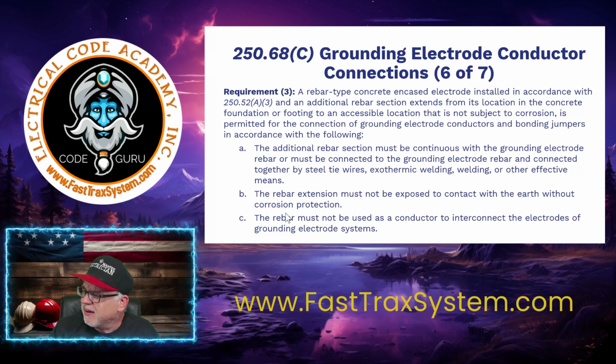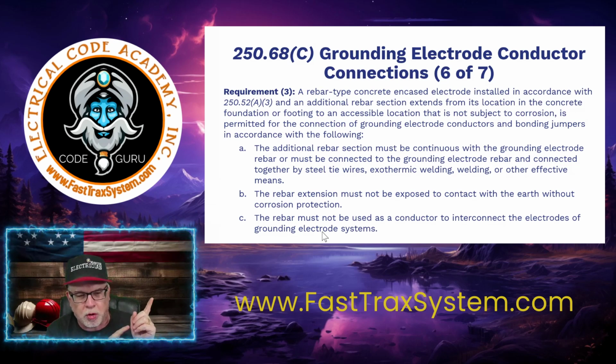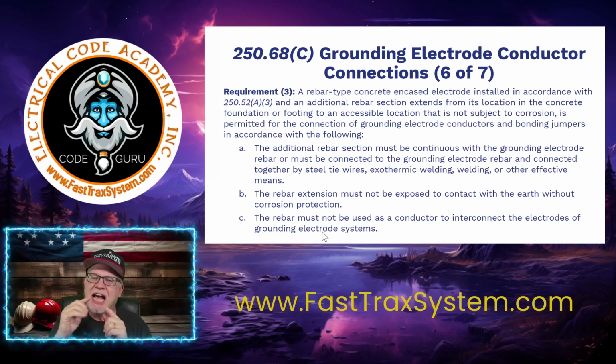Third, or C, it says the rebar must not be used as a conductor to interconnect the electrodes of the grounding electrode system. So that piece that's poking up is only for you to make a connection to that concrete encased electrode. That piece of rebar is not to be used as an interconnection for other electrodes, like we talked about with the water pipe, that 5 feet of water pipe. You're not going to use that little piece to do that. Not going to do that at all.